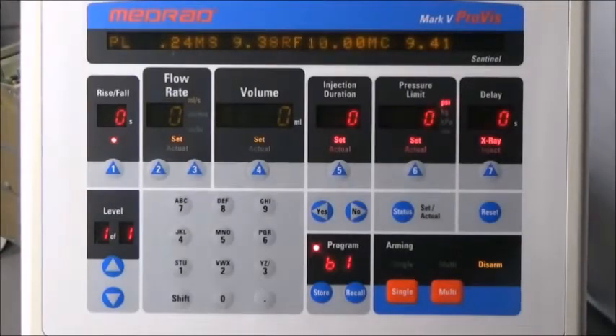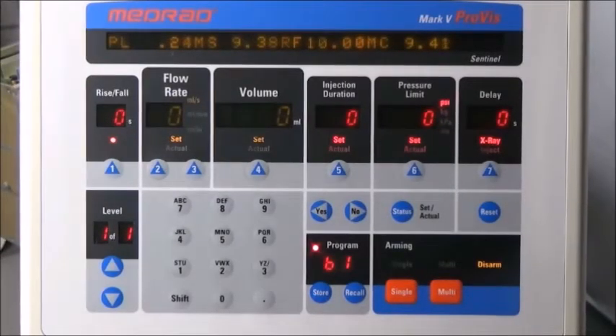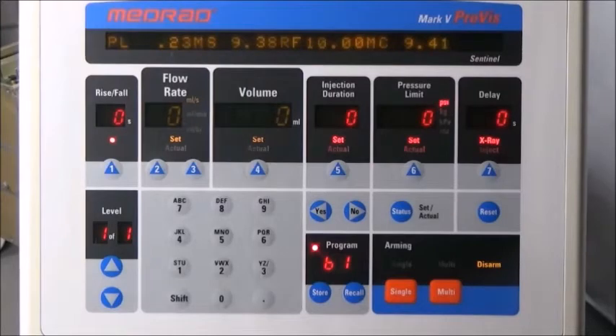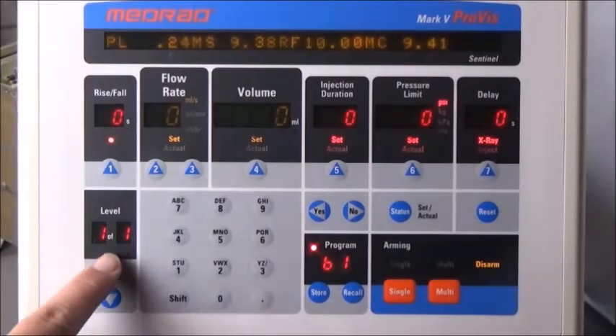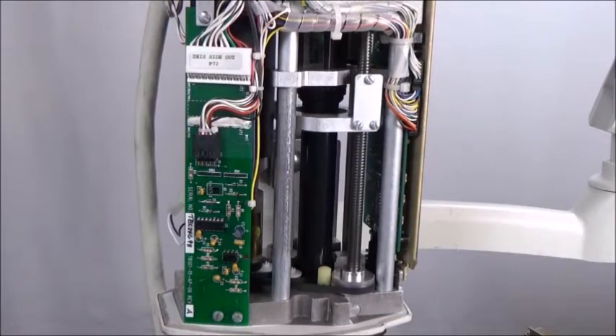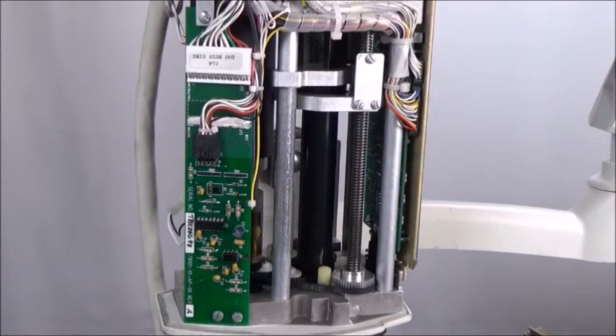This test checks, and if necessary calibrates, the R2 voltage, which is what determines the MS plate position. Press the level up arrow on the display. Because we are in this calibration mode, this causes the MS plate to move to what it thinks is its calibration position. This should be the position we need it to be in for calibration purposes, but it may not be exact. We may need to manually move the plate a little bit.